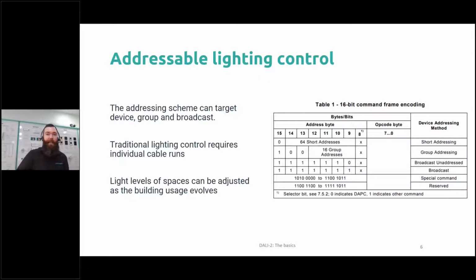In some other technologies, they would subsequently send this address or dim command to every single address, meaning some would receive it before others. On very fast moving systems, you might see some lights turn on or off before others in the same room. But when you use a group, every single light hears that command at the same time, and even though it's slow, it's able to start that dim process, moving from the first level to the next, at the same speed.